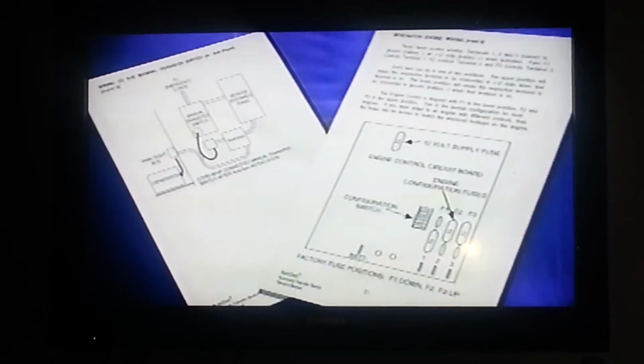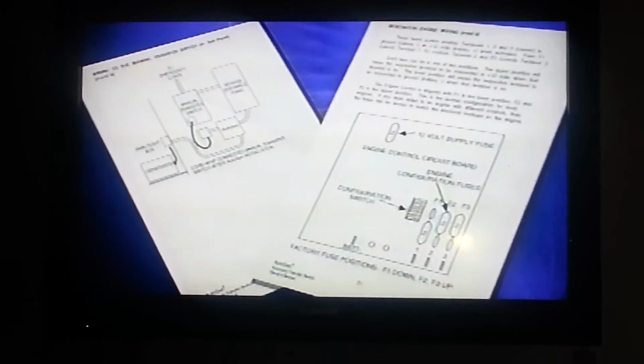Before proceeding, consult your installation instructions to determine the proper method for wiring the ATS transfer switch to your manual transfer switch. Run wires through the knockout in the left-hand side of the ATS transfer switch. Connect these wires to the load connectors located in the upper left corner of the ATS transfer switch. Be sure to use the correct amount of torque when tightening all connections.